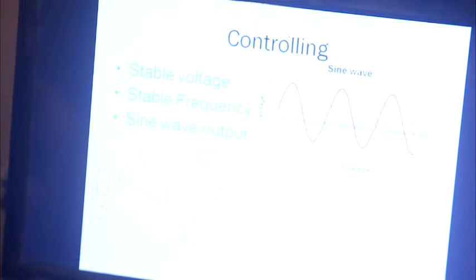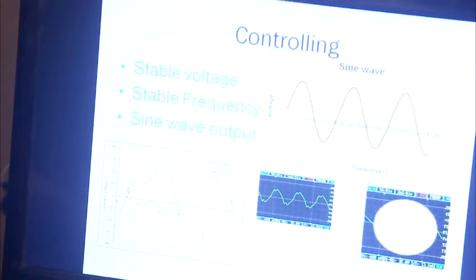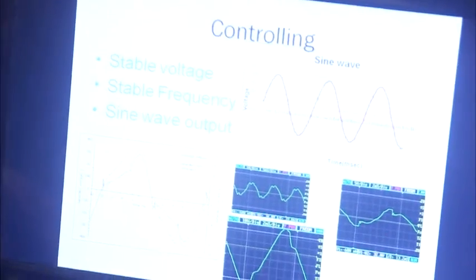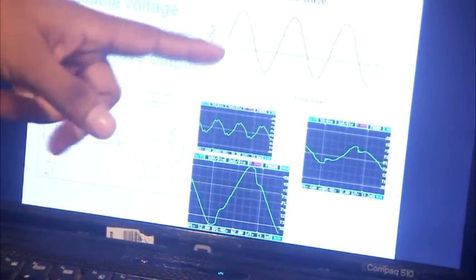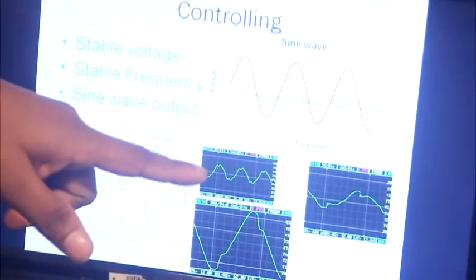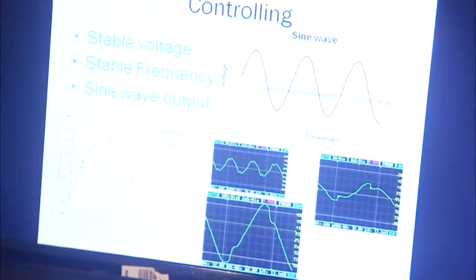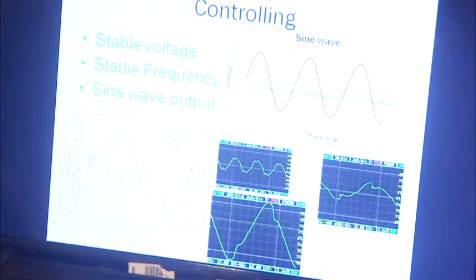The sine wave is mathematically shown in a graph, but due to bad features of some controllers, this sine wave is distorted. There is a lot of problem creation due to this distortion of the waveform. I have some pictures from an oscilloscope taken from a few types of available hydropower controllers. This is the best type of waveform from the national grid, but this is the waveform given from micro hydropower controllers. You can see a lot of distortion in the waveform. These are serious effects — generators burn out suddenly and maintenance cost increases drastically.